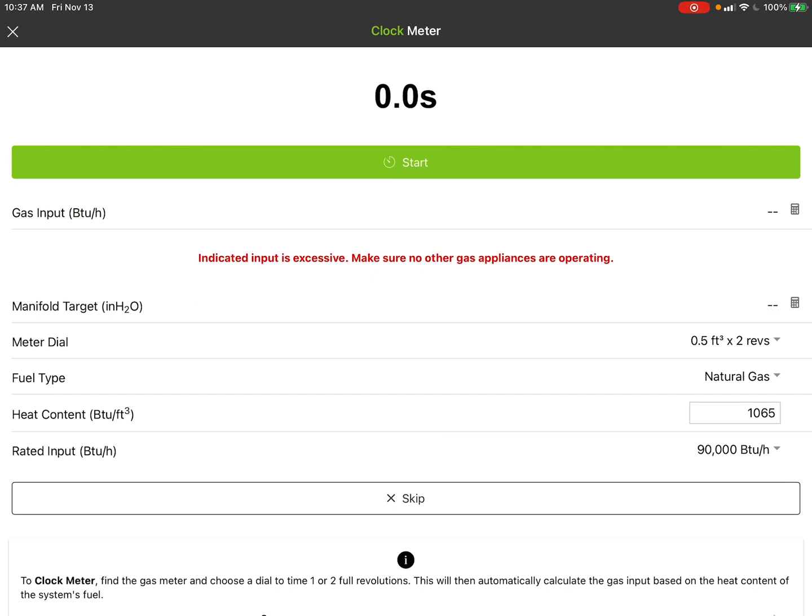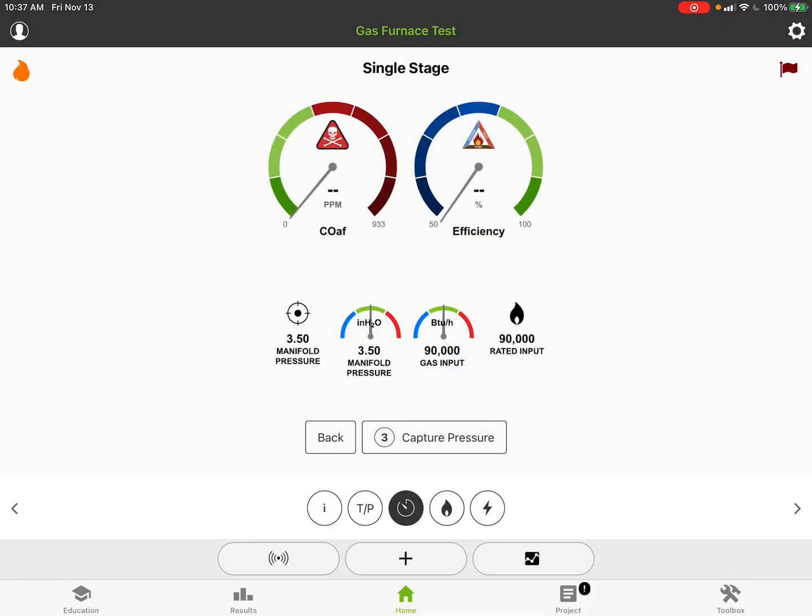It's going to assume that at 3.5 inches of water column, it's 90,000 BTUs of input. But again, that's not clocking the meter. If we hit the back screen here, we hit clock the meter.